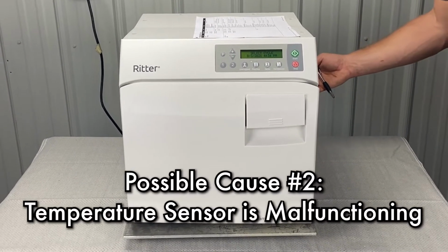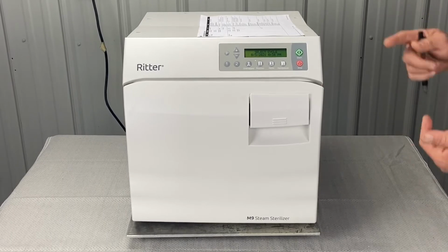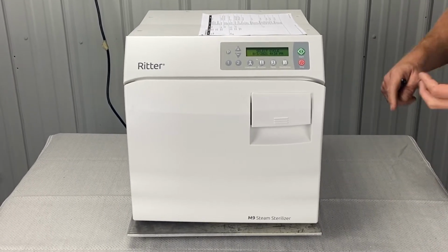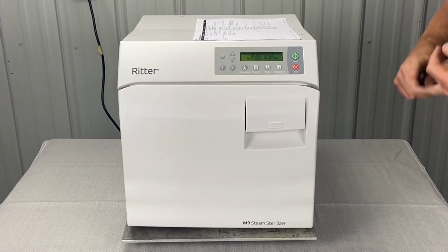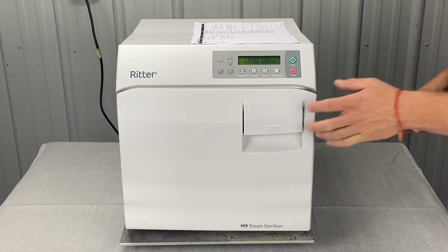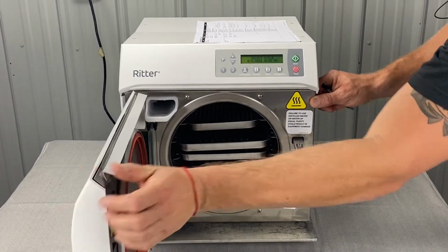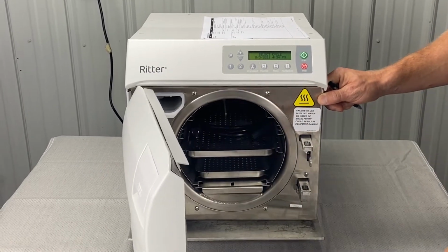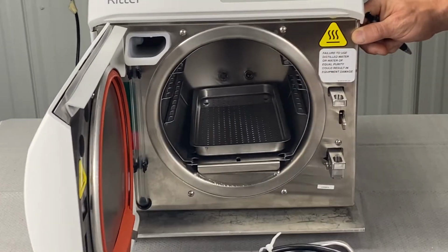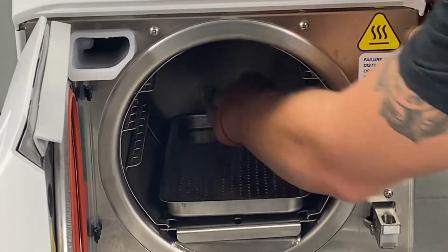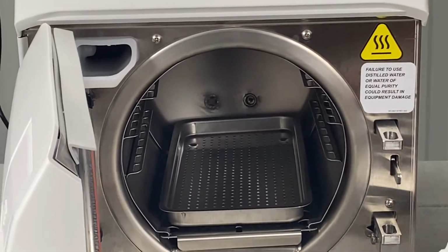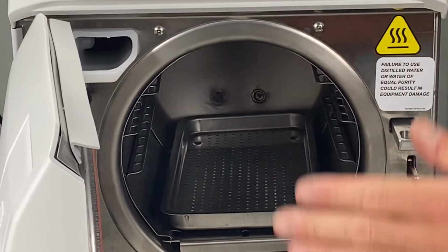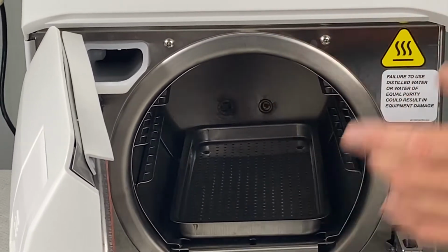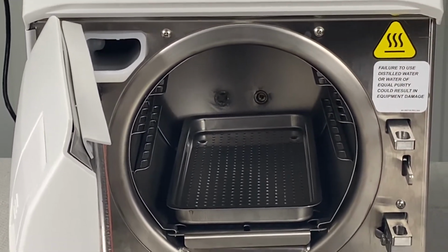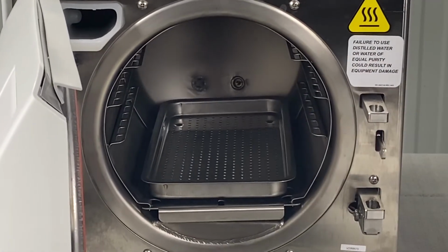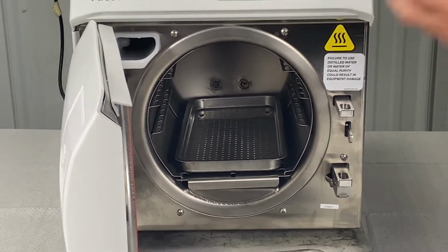the temp sensor is malfunctioning. There could be residue buildup on the temp sensor probe. It could be that things are clogging, touching, or crowding the temp sensor itself. The temp sensor is right in the back center, right here. If you stuff all these trays and all this stuff on top of it and smash it all in there, it could crowd it, it could sit on it, and give funky readings.